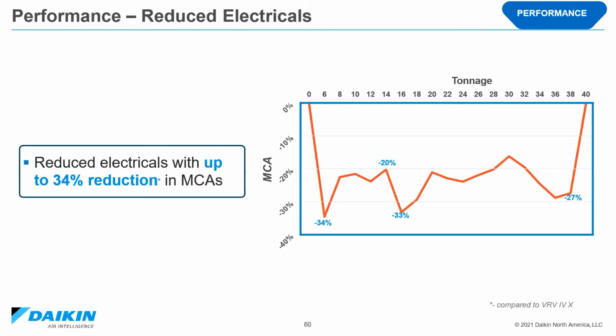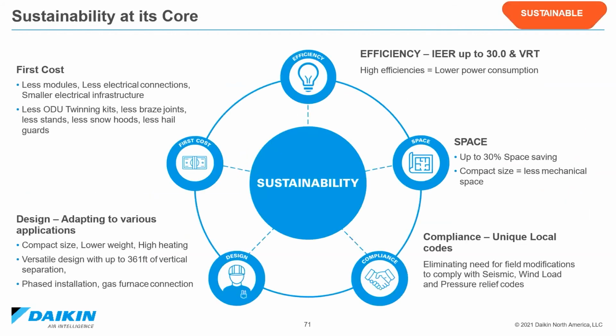Due to the increased efficiency of the new line, the electrical requirement has been dropped across the board, thus reducing MCA levels up to 34%. As this new platform is released, customers are going to see reduced first cost of the installation with the benefits of less modules, less electrical connections, smaller overall electrical infrastructure. More compact size and lower weight is going to provide additional benefits. And then the higher system efficiencies will aid end users as we're seeing utility costs increasing worldwide. In addition, the new Emerion units have code compliance addressing seismic, wind load, and pressure relief codes.